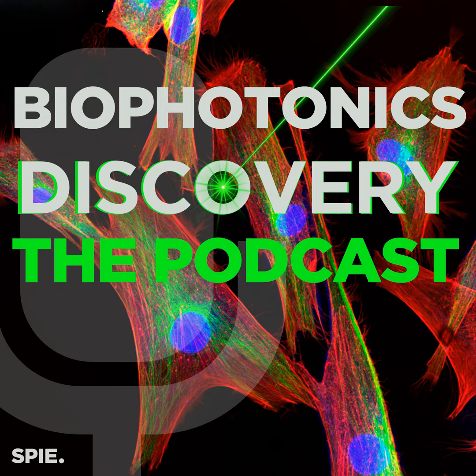So for the new features, we worked on integrating this camera module with LEDs. We have 8 high-power white LEDs, a lens, a CMOS sensor, and a sapphire glass window in this camera module that we developed alongside our industry partner, Misumi. We got this package down to a 5.5 millimeter outer diameter so it can fit in those trocar ports. We worked to change the lens system to have an optimal working distance of 3 to 7 centimeters. So here you can see we have improved resolution even at these longer working distances. And these are the range of working distances that are traditionally used in laparoscopic surgery.